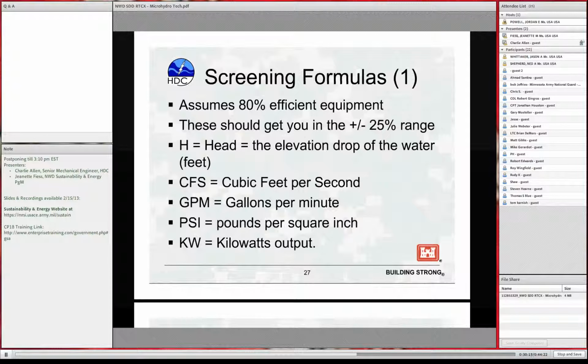Now, moving on to some screening formulas that you can use to go out and look at that site that you have to see if it, shall we say, cuts first muster. The formulas will be on the next slide. We have to slog through the upfront information first. I've assumed an 80% efficiency on the equipment. Equipment efficiency actually varies from about 60% to 90%. 80% is a good middle of the range. The formulas on the next slide will get you in the plus or minus 25% range. And if at plus or minus 25% you think it's still viable, it's time to start calling other people.